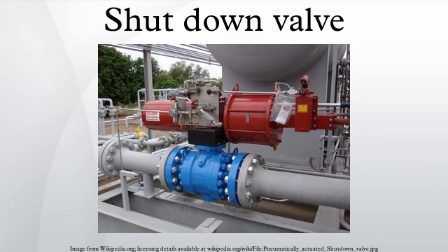For air intake shutdown, two distinct types are commonly utilized: butterfly valves and swing gate or guillotine valves. Because diesel engines ignite fuel using compression instead of an electronic ignition, shutting off the fuel source to a diesel engine will not necessarily stop the engine from running. When an external hydrocarbon, such as methane gas, is present in the atmosphere, it can be sucked into a diesel engine causing over-speed or over-revving, potentially leading to a catastrophic failure and explosion.